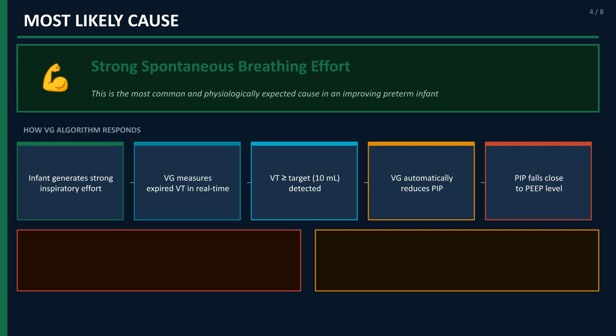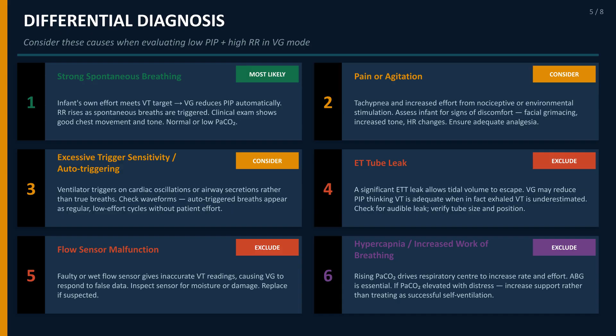When evaluating low PIP with high RR in VG mode, the differential diagnosis begins with the most likely cause: strong spontaneous breathing. Other causes to consider are pain or agitation, which would lead to tachypnea and distress. Excessive trigger sensitivity or auto-triggering may also mimic this, so checking waveforms is essential. Excluded causes, if the tidal volume target is met, include ETT leaks or flow sensor malfunctions. Also excluded is hypercapnia-driven increased work of breathing if ABGs are normal.